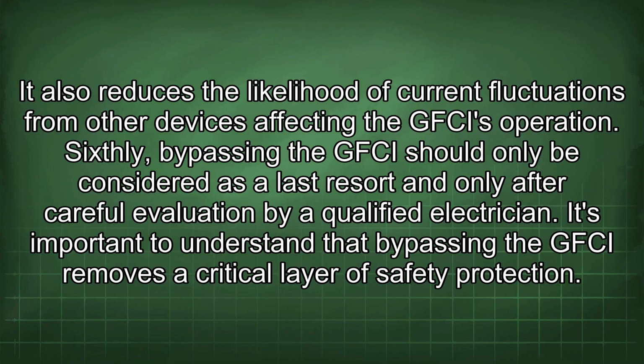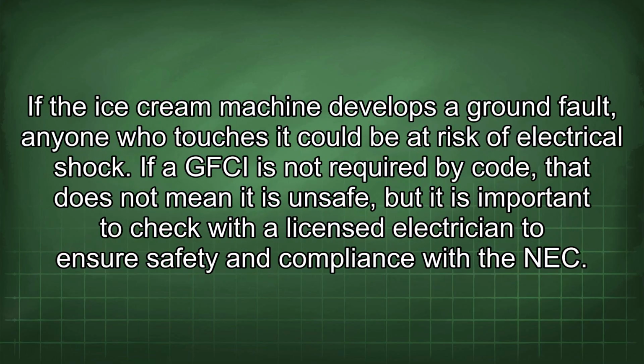Sixthly, bypassing the GFCI should only be considered as a last resort and only after careful evaluation by a qualified electrician. It's important to understand that bypassing the GFCI removes a critical layer of safety protection. If the ice cream machine develops a ground fault, anyone who touches it could be at risk of electrical shock. If a GFCI is not required by code, that does not mean it is unsafe, but it is important to check with a licensed electrician to ensure safety and compliance with the NEC.